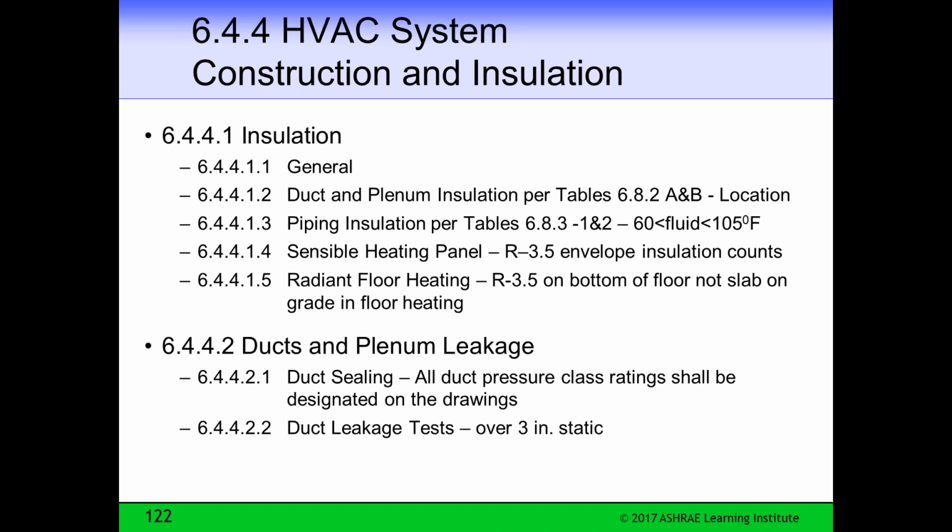Now, ducts and plenum leakage. Duct sealing: all duct pressure class ratings shall be designated on the drawing. So you've got to show what the duct class rating is, which is the pressure in the duct. And then all sealing must be class A, no matter what that pressure class rating is. If you look at SMACNA, it has class A, B, and C type duct sealing. We want you to seal the duct to class A all over the building.